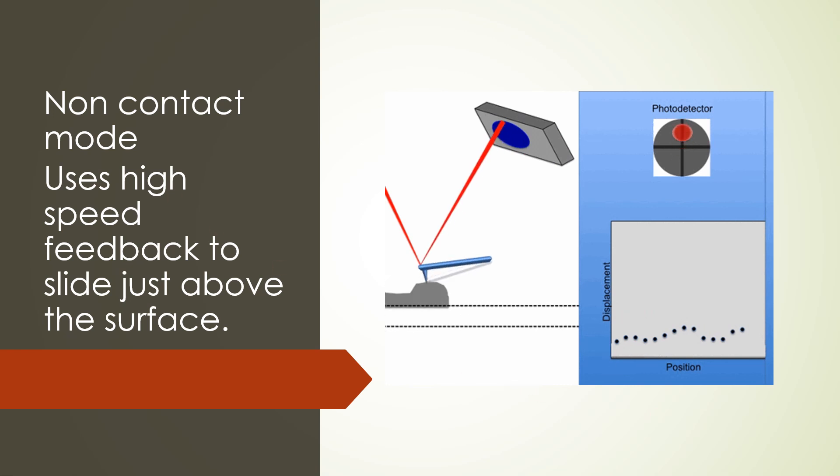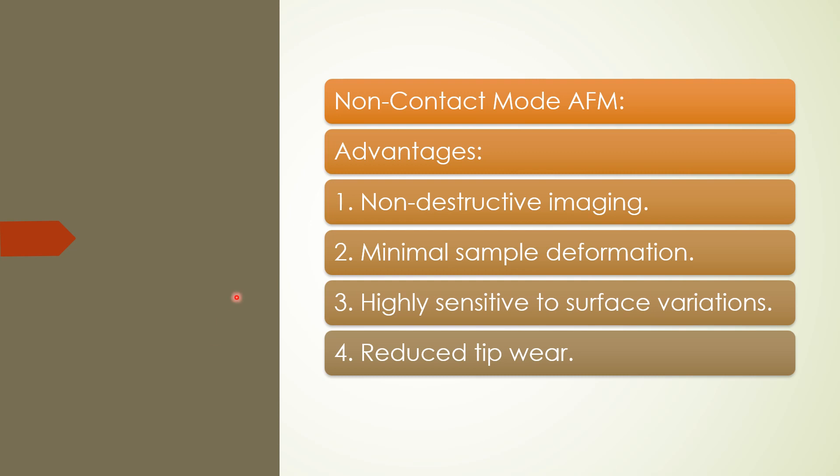The recorded plot is analyzed for the desired purpose. The advantages of operating in non-contact mode include non-destructive imaging, minimal sample deformation, and high sensitivity to surface variation. There is also reduced tip wear because the tip is not in contact with the sample — so neither the sample nor the tip is damaged — and the tip can be used for a longer time, reducing operating cost.